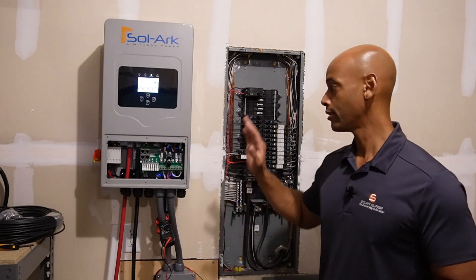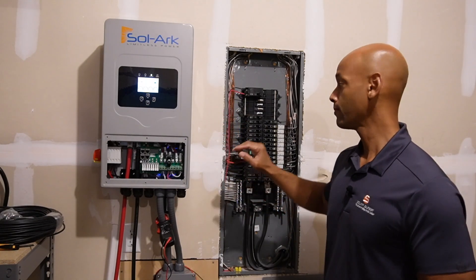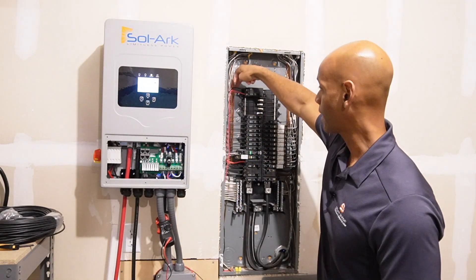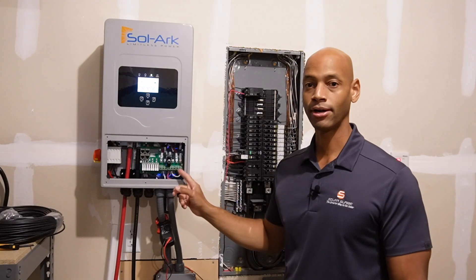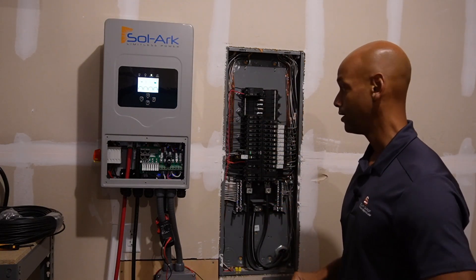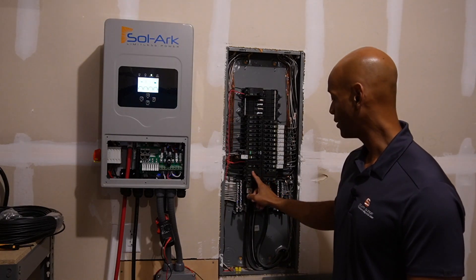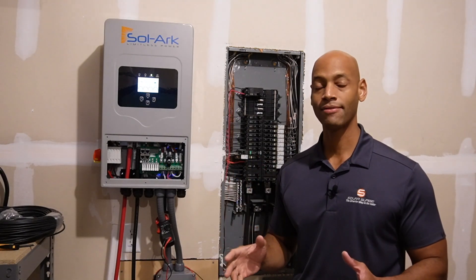Key point: you have to make sure that your main disconnect outside is turned off, or if you have a main breaker, make sure that your main breaker is turned off before you back-feed like this. I actually have the line output on the Sol-Ark double-tapped, which means I'm feeding both the black line one conductor and the red line one conductor from the same terminal — coming off the same phase on the Sol-Ark — so I can feed both poles on my load center. The Sol-Ark 5K is powering the entire house with the exception of three circuits: the air conditioner, the electric clothes dryer, and the electric range — the only three 240-volt loads at the house.